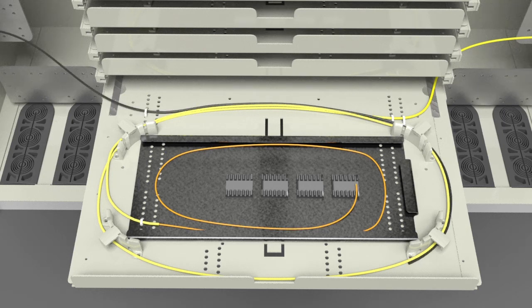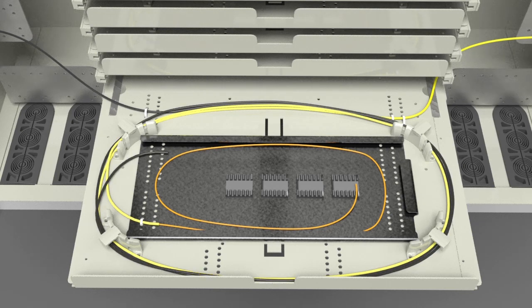Route the OSP subunit clockwise around the radius limiters and enter the splice tray at the left side top. Secure the subunit to the tray.